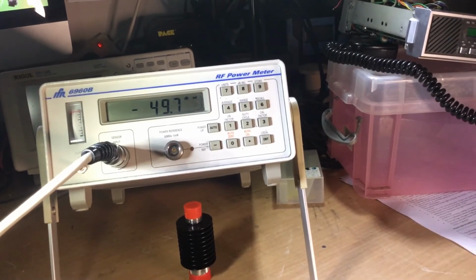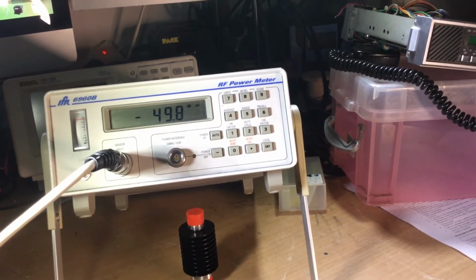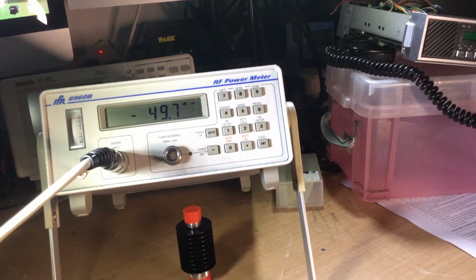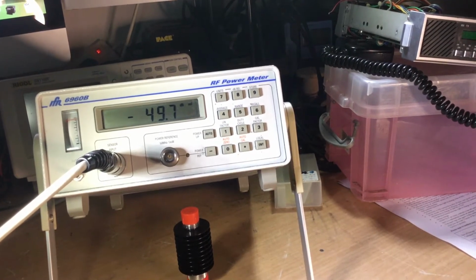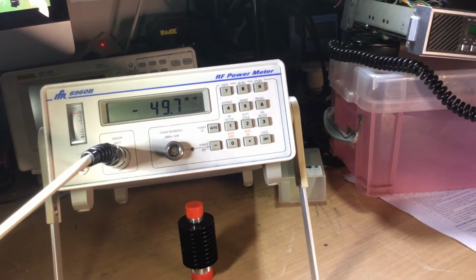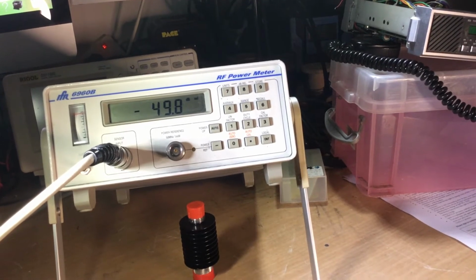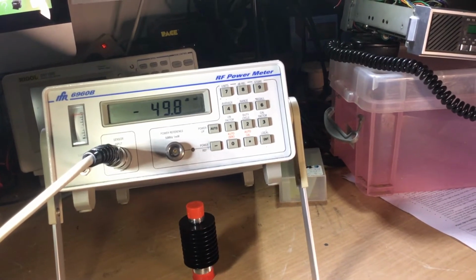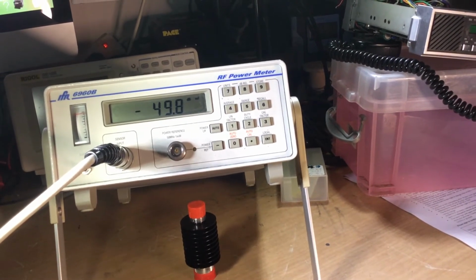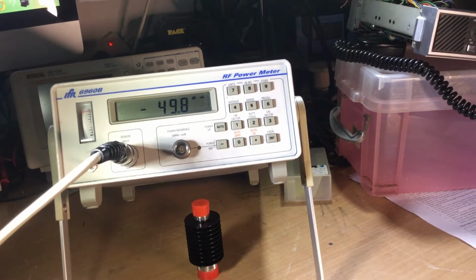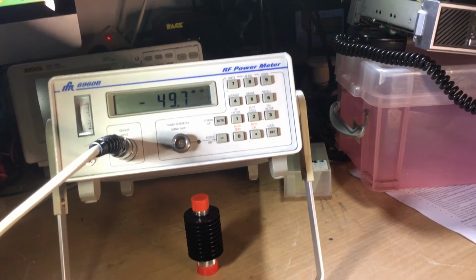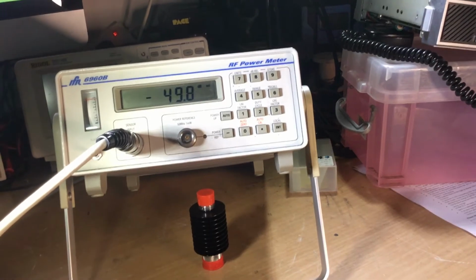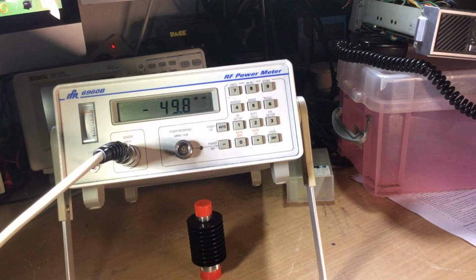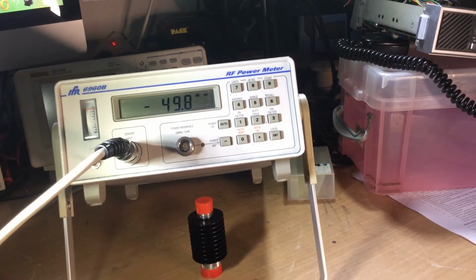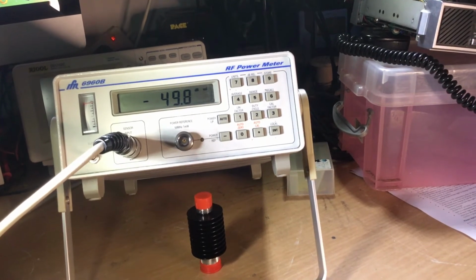So regarding noise, it says for applications needing a fast response on sensitive range, the user can trade off resolution for speed by entering a low average number. The 6960B accepts average numbers between 1 and 256, so optimum noise reduction or required response time are always available.